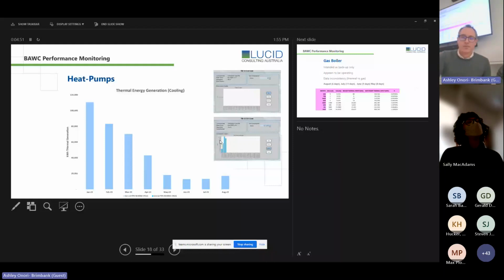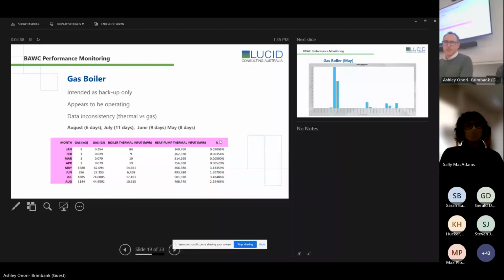So in terms of gas, this is probably the key thing that everyone wants to know. The gas boiler was intended as backup only and to provide redundancy under key events where the pool has to be drained down and then refilled with water and then heated back up very quickly. It does appear to be operating, and what we've got here is the gas consumption, cubic meters converted to gigajoules, the boiler thermal input, which is estimated from the gas consumption, versus the actual thermal input from the heat pumps themselves. So you can see that the gas boiler is kicking in, but it's a very, very small amount.